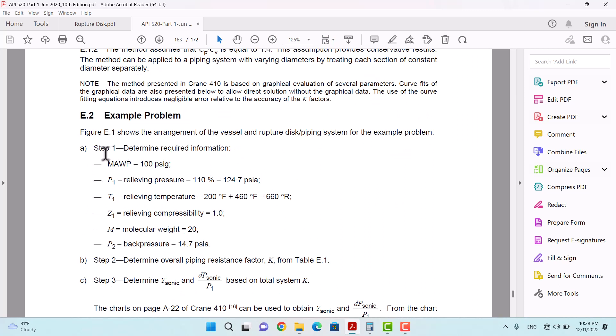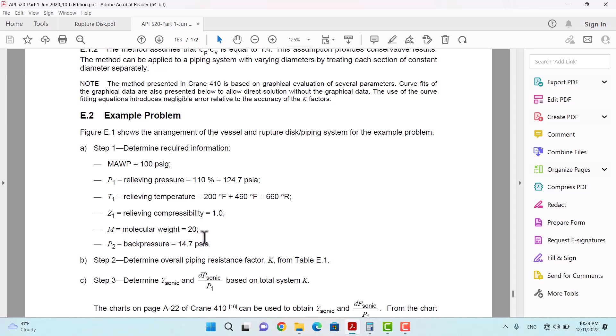In the first step, we determine the required information. The maximum allowable working pressure is 100 PSIg, so the relieving pressure with 10% accumulation is 124.7 PSI absolute. The relieving temperature must be converted from Fahrenheit to Rankine. The relieving compressibility is 1, the molecular weight is 20, and the back pressure is atmospheric pressure, which is 14.7 PSI absolute.